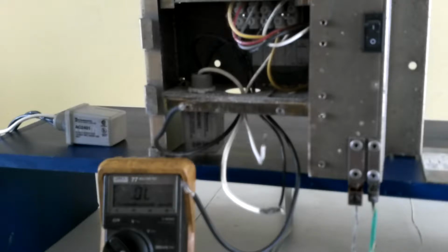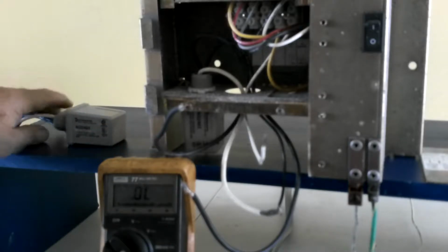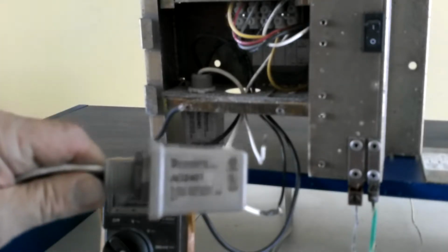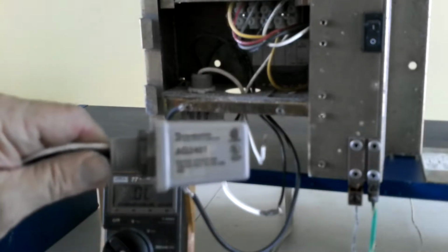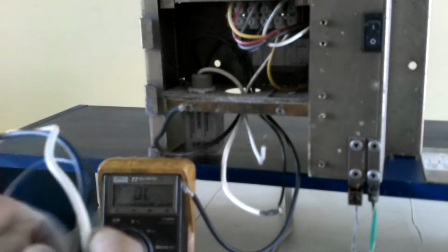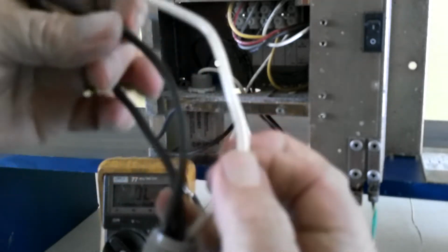Today we're going to talk about the proper installation of an external surge arrestor to help protect your field satellites from heavy surge or lightning. Surge arrestors typically are a small cube-shaped device that have a threaded nipple mount configuration. They also have 3 wires coming out of them, typically 2 black and 1 white.